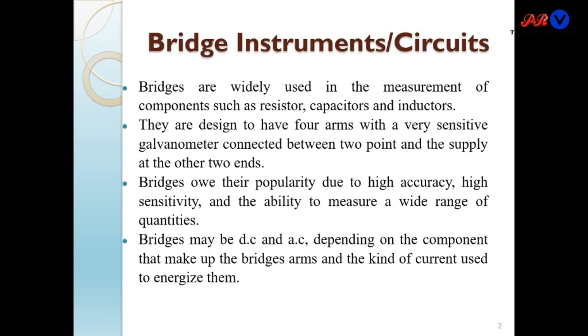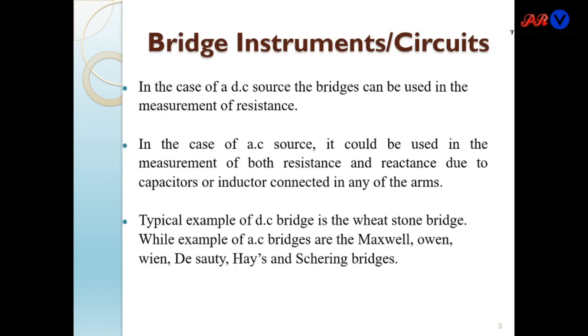DC bridges are used to measure only resistance, while AC bridges can measure resistance, inductance, as well as capacitance. In the case of an AC source, it could be used in the measurement of both resistance and reactance — inductive reactance or capacitive reactance — due to capacitors or inductors connected in the arms. A typical example of a DC bridge is the Wheatstone bridge, while examples of AC bridges are the Maxwell bridge, Owens bridge, Wien bridge, Desauty bridge, Hay bridge, and Schering bridge.